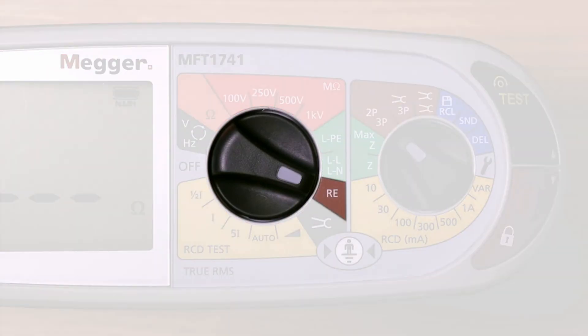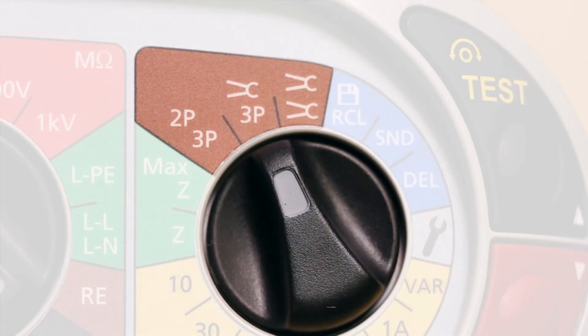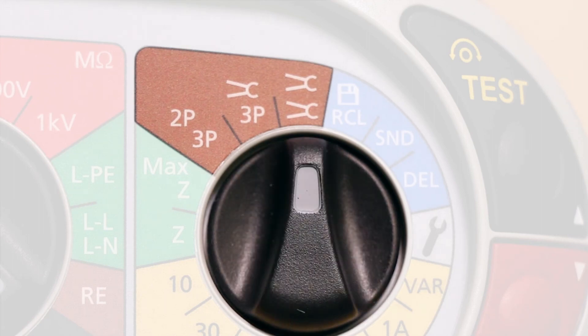Finally there is an earth electrode or ground stake resistance test which is enabled for standard three wire testing, ART or attached rod technique, and the stakeless test method.